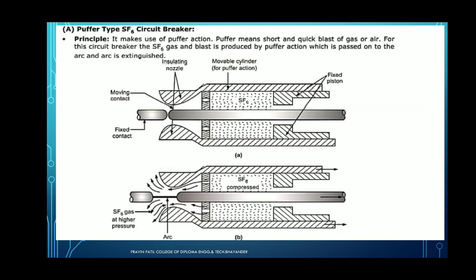Here, the main components of the SF6 circuit breaker are the insulating nozzle, moving contact, fixed contact, movable cylinder, and fixed piston. If a relative movement between the fixed piston and movable cylinder takes place, then compression of the gas takes place, and some gas leaks through the nozzle valve, and this gas acts on the arc, and the arc is easily extinguished with the help of SF6 gas. So this is the working principle of the SF6 circuit breaker.